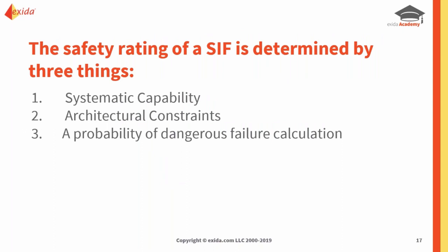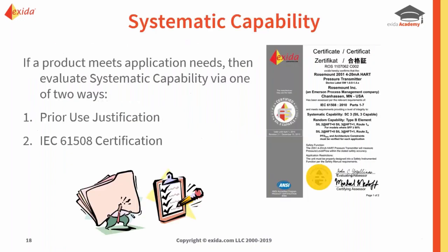There are different barriers that engineers face when they perform a SIF design. When an end user is choosing a device to incorporate into their SIF, there are three major barriers they must hurdle over to say the SIF is in compliance with IEC 61511 and to really achieve that SIL rating. The SIL level is determined by three things: the systematic capability rating, the architectural constraints for that element, and the PFD average calculation for that product.